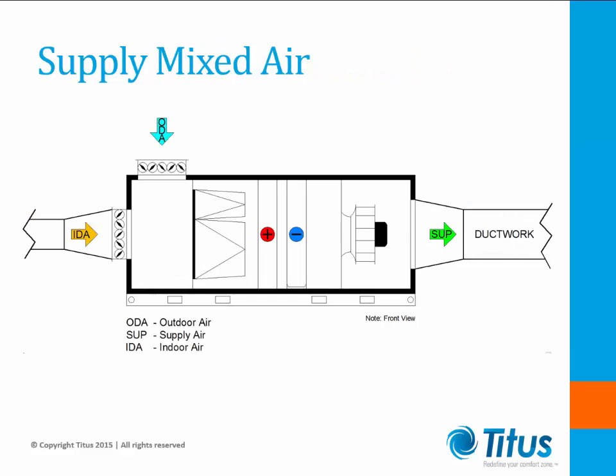The next configuration example is of a supply mixed air design. The layout is very similar to the 100% supply air configuration with an added return air duct. This configuration allows outside air to be mixed with return air from the building to meet acceptable air changeover requirements for fresh air. The mixing of the two types of air can aid in lowering the overall energy usage of the AHU that heats or cools the building.